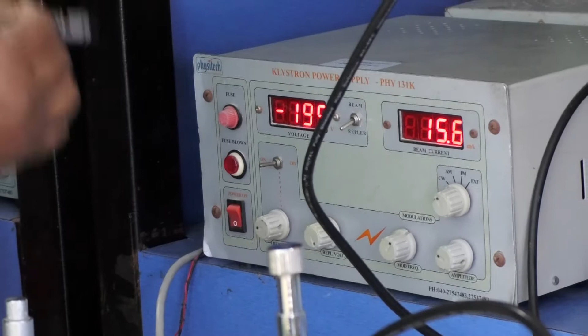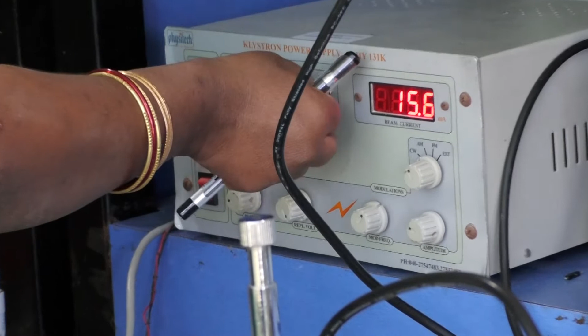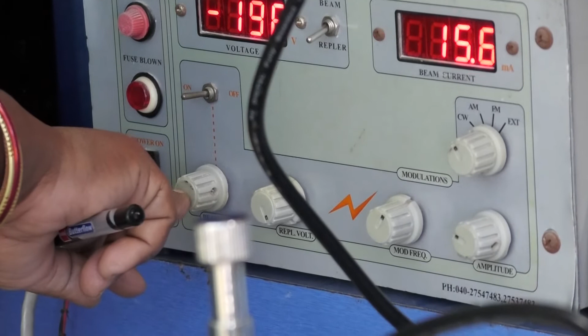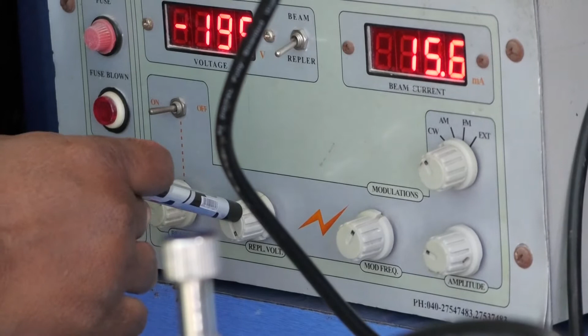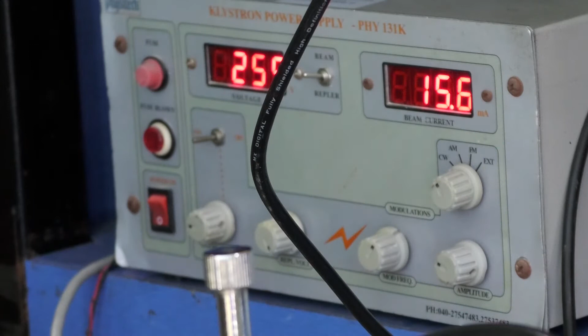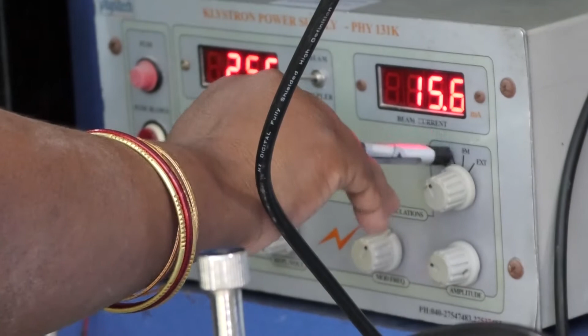It consists of two different voltages like beam voltage and repeller voltage. Beam voltage should be always present in anti-clockwise direction, and repeller voltage should be always in fully clockwise direction. That beam voltage should be less than 300 volts, such that we have to adjust the beam voltage, and beam current should be less than 30 milliamperes. Here the klystron power supply has four different modes of operation. Normally we prefer AM mode of operation to do the experiments.